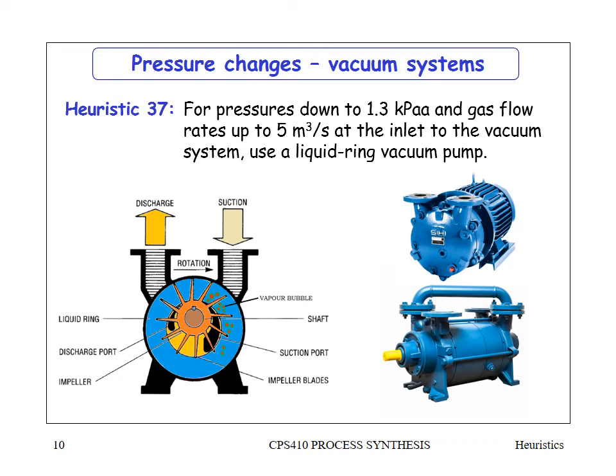When you need to get down to 1.3 kPa and gas flow rates up to five cubic meters per second at the inlet, use a liquid ring vacuum pump — like those found in laboratories. They use a liquid ring to prevent leakage. Five cubic meters per second is a significant flow, but not a large mass flow since 1.3 kPa is only about 1.3% of atmospheric pressure.